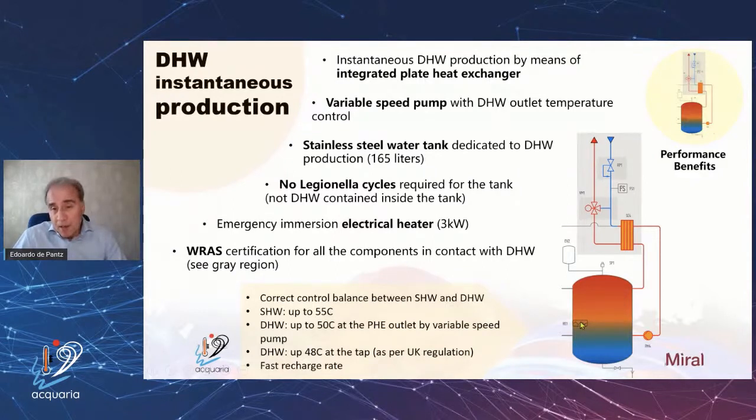There is also a backup heater as an emergency. So this backup heater is not working during the normal function of the unit, of the domestic water production, but only in case of emergency. In any case, the Legionella cycle can be activated for service reason if there is the request, but not for the normal functioning of the life of the unit. In the tank we have typically 55 degrees in order to have 50 degrees at the outlet of the heat exchanger, and then 48 degrees at the tap, as per the UK regulation.